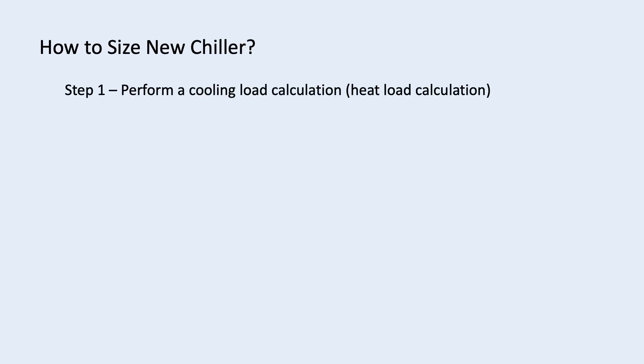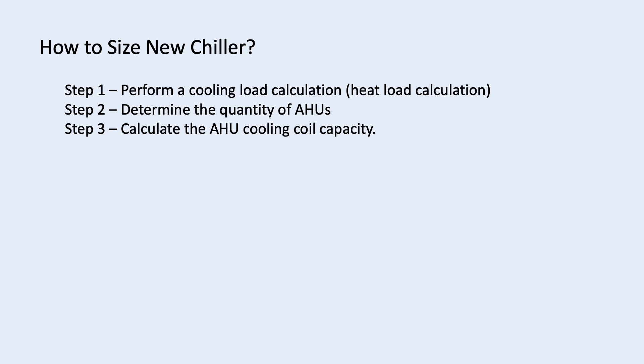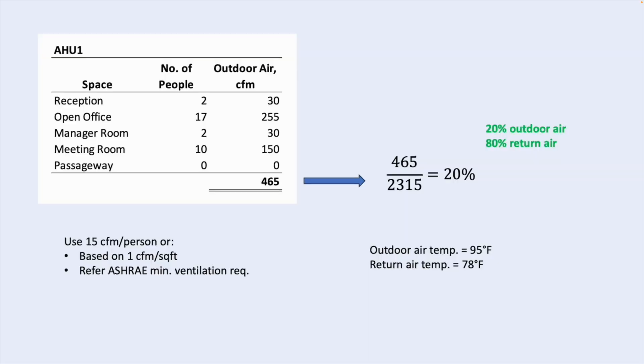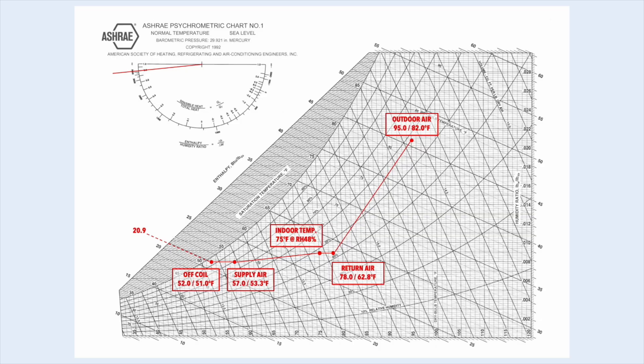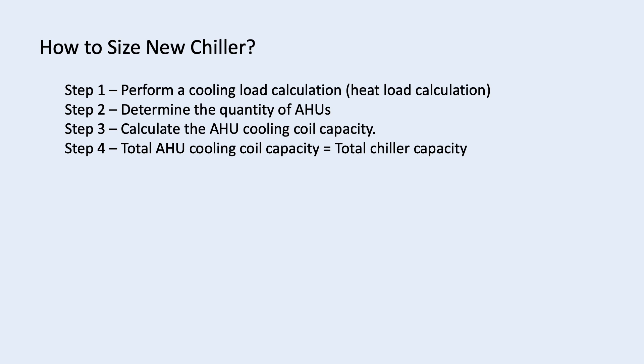For new chiller capacity calculation, step 1 is perform a cooling load calculation. We need to know how much heat needs to be removed. Step 2 is determine the quantity of AHU. We need to divide the space in the building and decide which AHU serves which area. Step 3 is calculate the AHU cooling coil capacity. In my video about AHU cooling coil design calculation, I explained that we need to account for outdoor air, fan motor heat gain and duct losses when sizing the AHU. And for the final step, the sum of all AHU capacity is the total chiller capacity that you need.